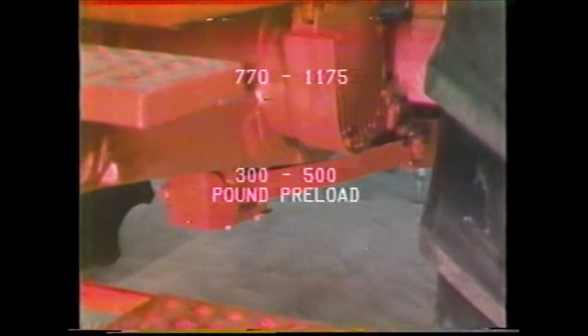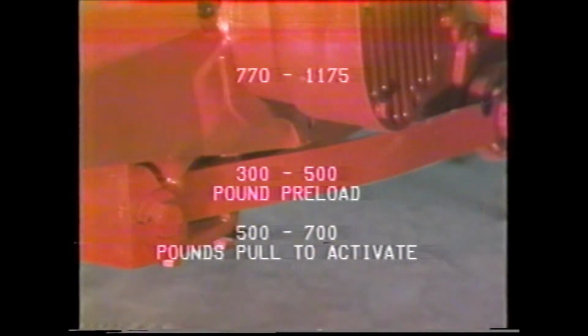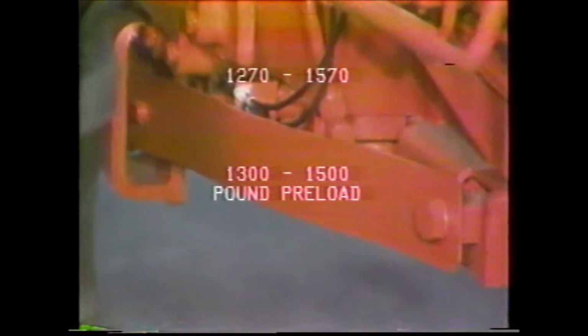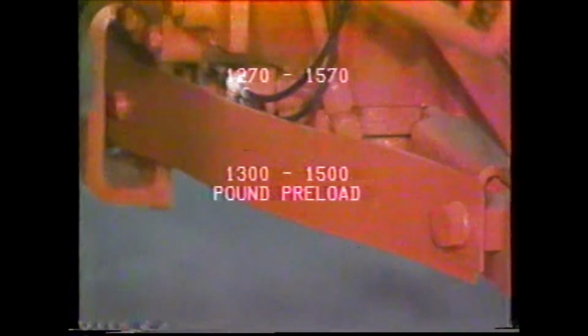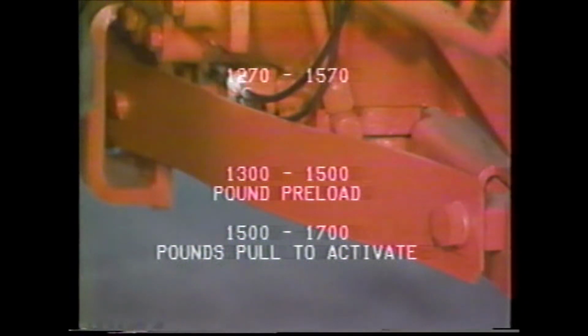Thus, the 770 through 1175, which has a 300 to 500 pound spring preload, will require 500 to 700 pounds pull to activate the Draft-o-Matic. The 1270 through 1570 has a 1,300 to 1,500 pound spring preload, requiring about 1,500 to 1,700 pounds of pull to activate the Draft-o-Matic. To measure the pounds of pull required to operate the Draft-o-Matic, it will be necessary to convert the pounds of pull to pounds per square inch, so it can be read on a hydraulic pressure gauge.